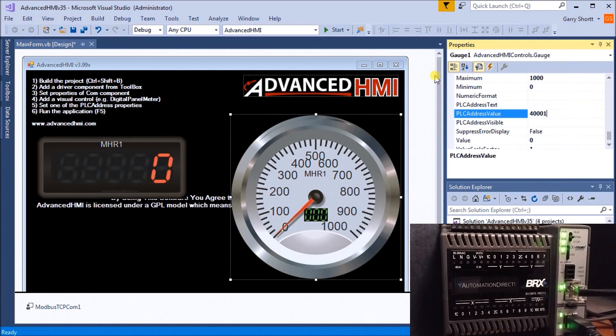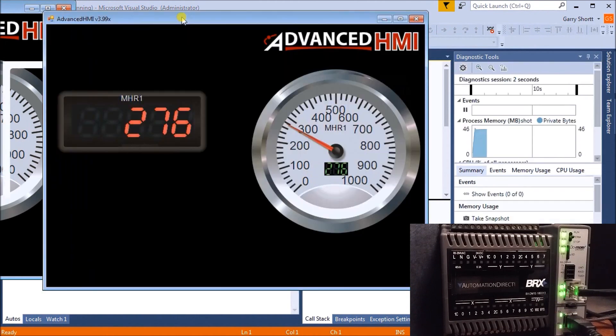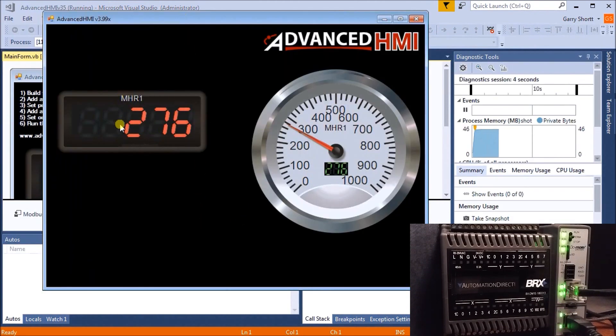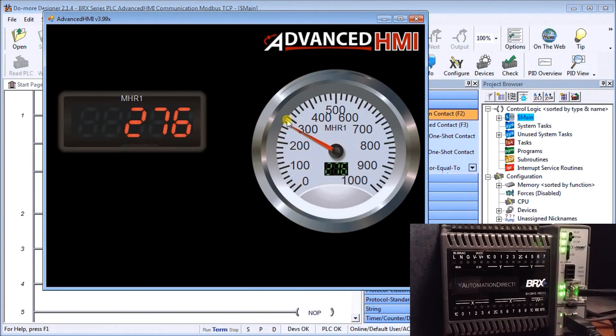We save the project and start it — it compiles and begins running. The gauge automatically populates with the value of MHR1. Going back to our program, you can see MHR1 is currently 276, which corresponds exactly to what our values are reading here — 276. And on our gauge itself we have the same value.